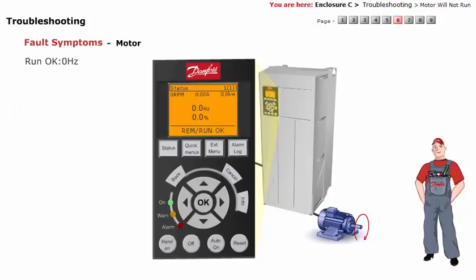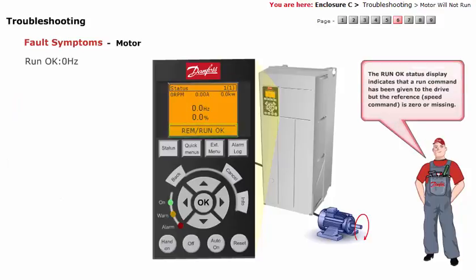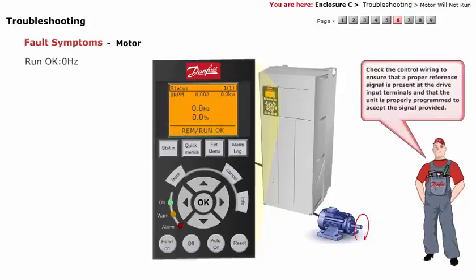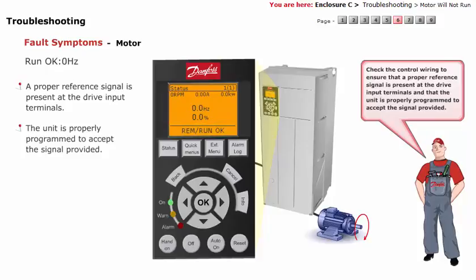Run OK Zero Hertz: The Run OK status display indicates that a run command has been given to the drive, but the reference speed command is 0 or missing. Check the control wiring to ensure that a proper reference signal is present at the drive input terminals and that the unit is properly programmed to accept the signal provided.